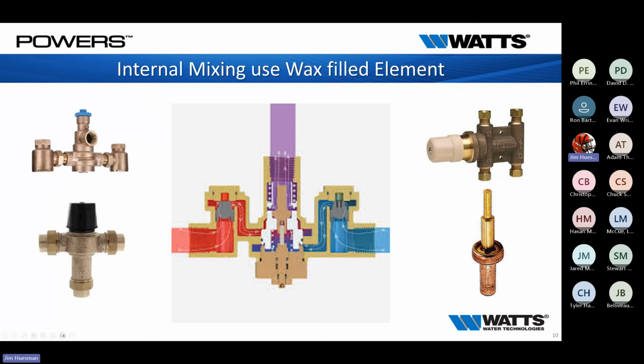So that's the whole theory: as we expand, we shut hot water off, allowing cold to go through; as we contract, we shut cold off, allowing more hot. So we're able to blend it back and forth, and all that blending is actually going to happen right in this area. As it passes through, it hits our element and all the features in here, starting to spin that water, mixing it right at that point, and then sending it out to our system.